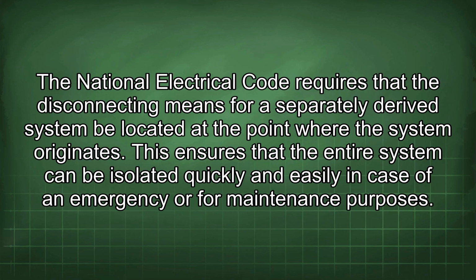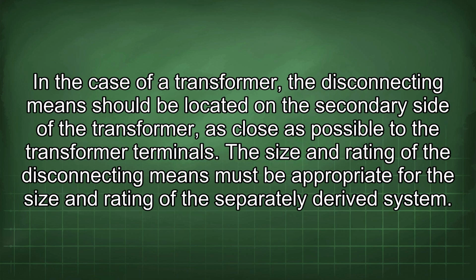The National Electrical Code requires that the disconnecting means for a separately derived system be located at the point where the system originates. This ensures that the entire system can be isolated quickly and easily in case of an emergency or for maintenance purposes. In the case of a transformer, the disconnecting means should be located in the secondary side of the transformer, as close as possible to the transformer terminals.